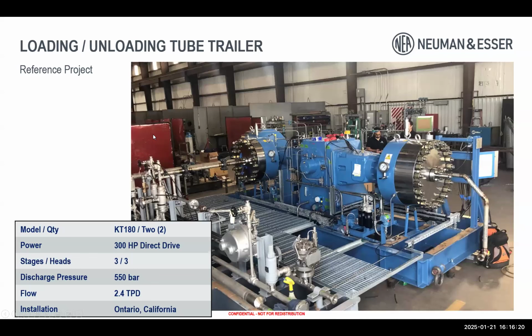The other example is a loading and unloading tube trailer application. This is a three-stage diaphragm compressor, 300 horsepower. This is as big as it gets on this type of technology. It is approaching the limit of diaphragm compression technology, 2.4 tons per day at 550 bar. And there are two of those, so there's a spare unit. This is installed in a facility in Ontario, California, feeding tube trailers of another major industrial gas company. So this is a configuration that I'm seeing quite often in heavy-duty refueling station projects.